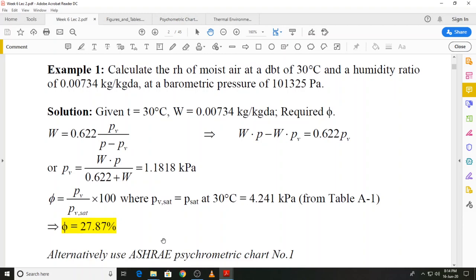In the first example, the dry bulb temperature and humidity ratio are given at a barometric pressure of 101,325 pascals, and the relative humidity is required. The relative humidity can be obtained by taking the ratio of the existing partial pressure of water vapor in air divided by the partial pressure of water vapor in air when that air sample becomes saturated at the given dry bulb temperature.